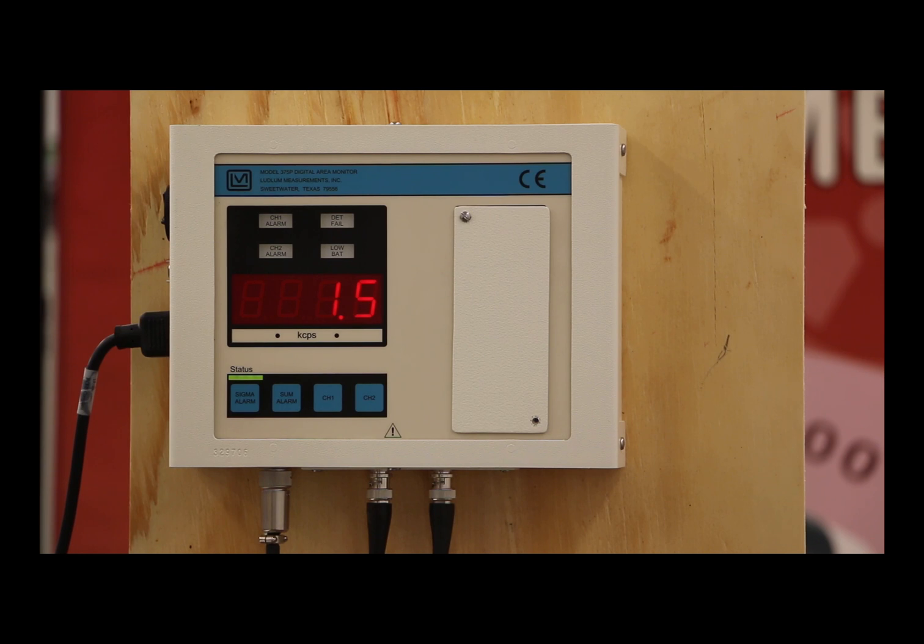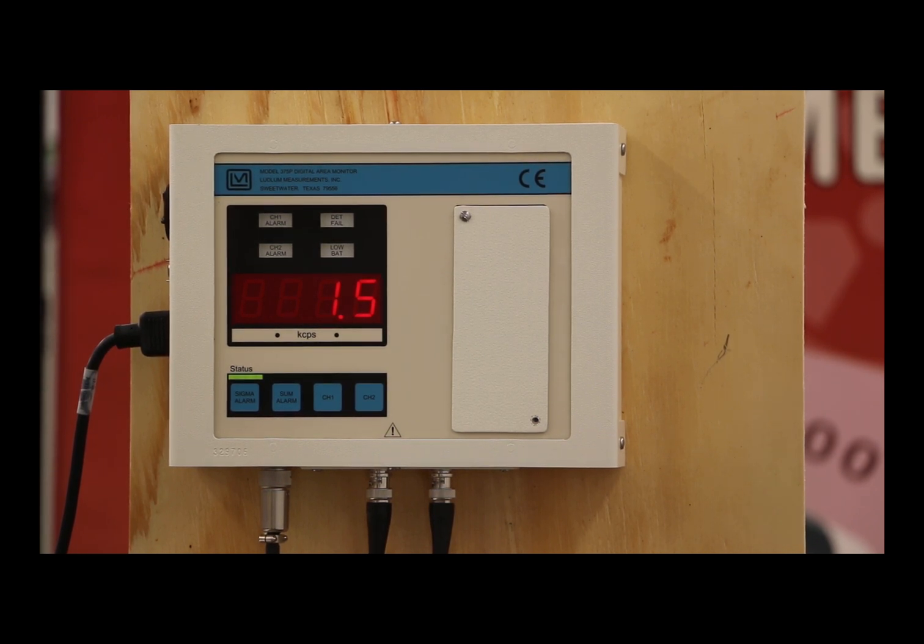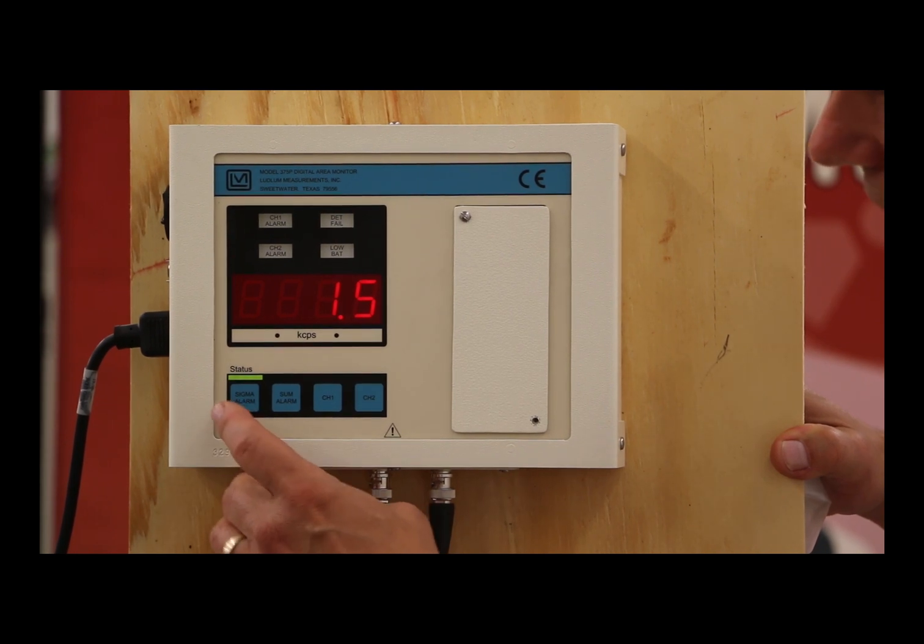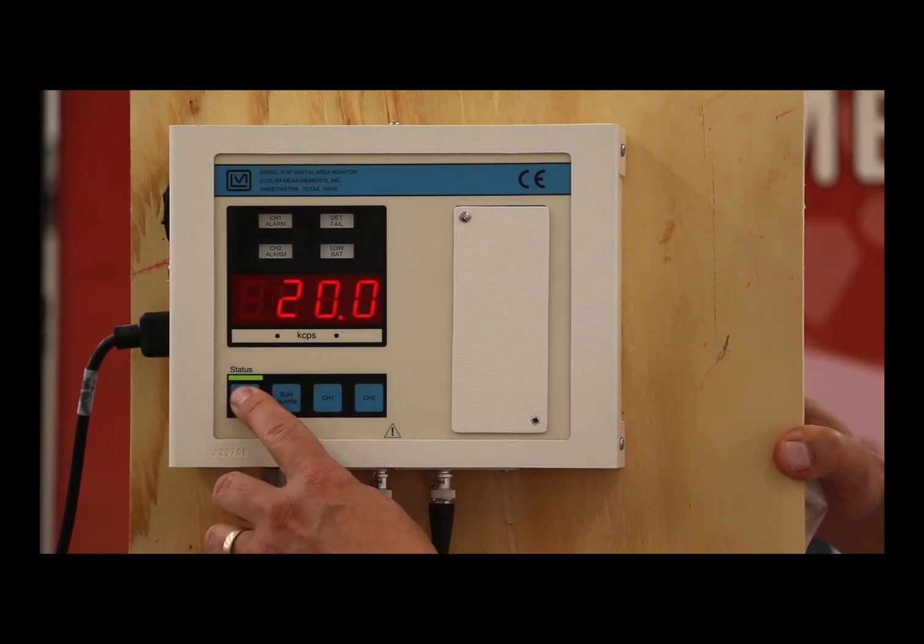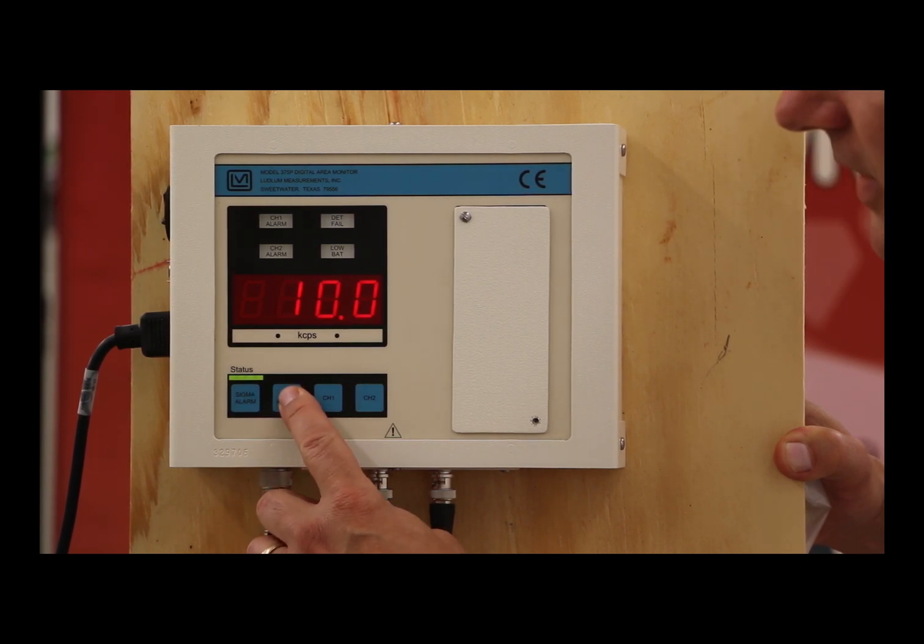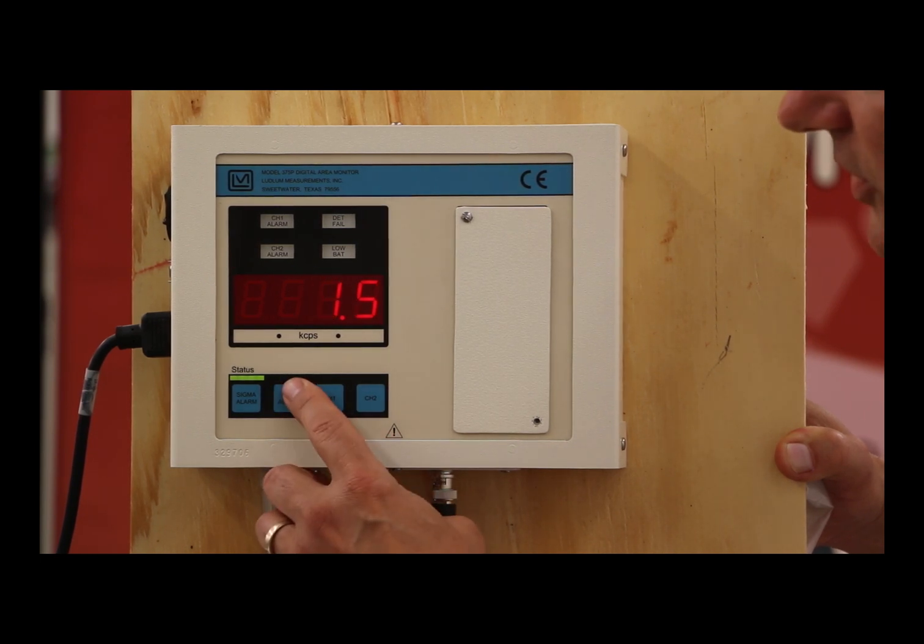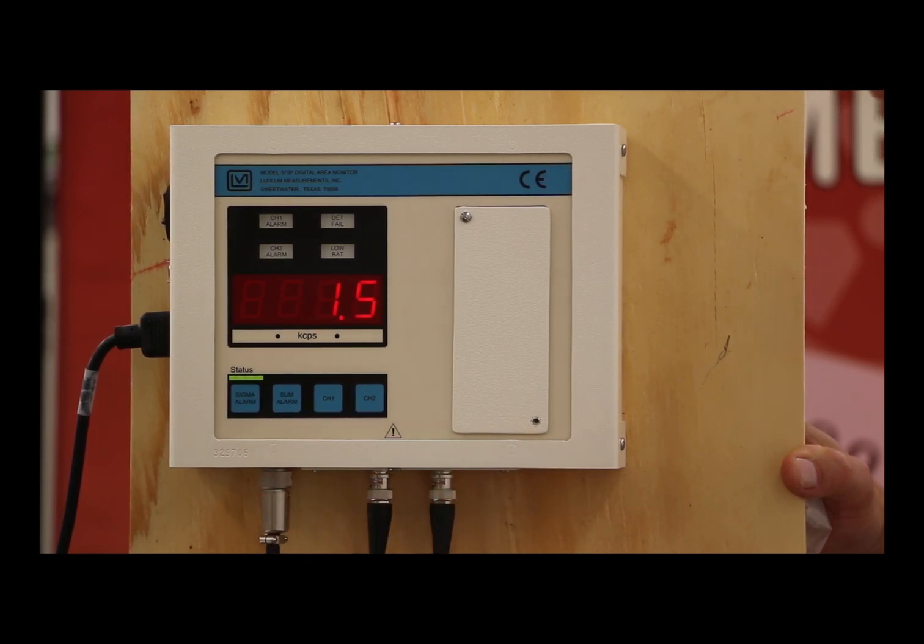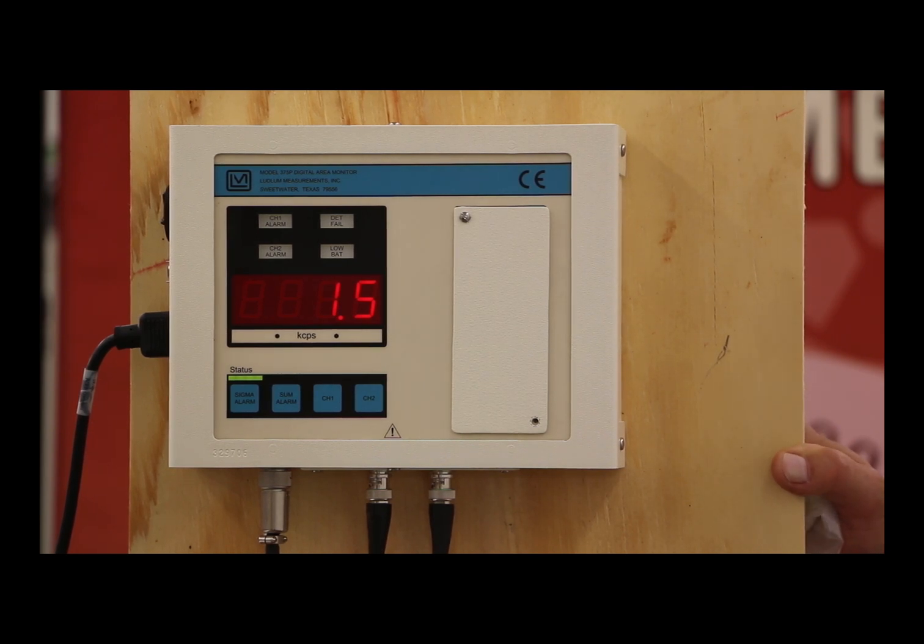The last thing I want to talk about is the setting of these alarms and how you can see that on the screen. If I push the sigma button, you'll see 20 sigma is the setting. If I push the sum alarm, you'll see that this is in terms of 10,000 counts per second is what the upper level is. As you can see, I'm sitting here at 1,500 to get to 10,000. That factory setting is quite a bit higher than what you're normally going to see in background.